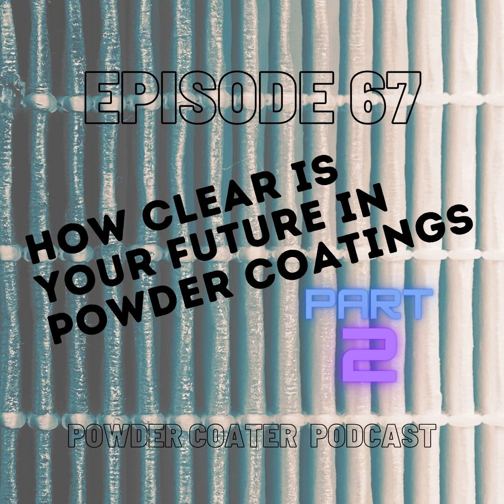But your turns, which is how many times that air volume inside the oven is turned over, because of CO, incomplete combustion, they're trying to prevent CO getting into any kind of atmosphere because we know that's really bad. Older, poorly maintained burners are much more likely to have a much higher percentage of CO. So they're not creating enough CO2, they're creating CO. Those carbon molecules have to go to something, so they're going to go to CO2 or they're going to go to CO. But if you're creating CO, you're often creating soot. It's another way you might have some issues.